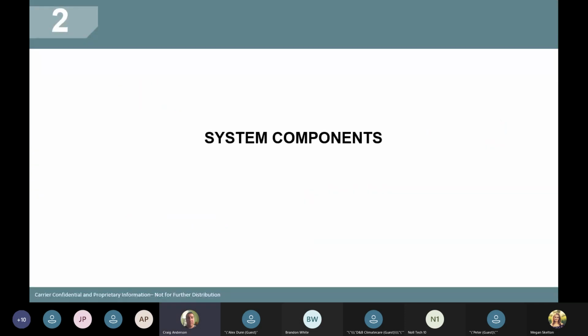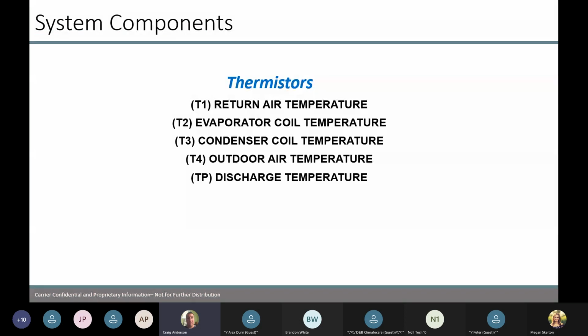So system components, this is how the unit is going to operate. So there's a bunch of thermistors out there: return air sensor, evaporator sensor, coil sensor, outdoor temperature sensor, discharge temperature sensor. They all do a different function to help this unit turn on and turn off and modulate. So we have to be real mindful of these sensors and that they are in the right location. If they have fallen off or something like that, that could give us sensor errors or erratic operation of the unit.